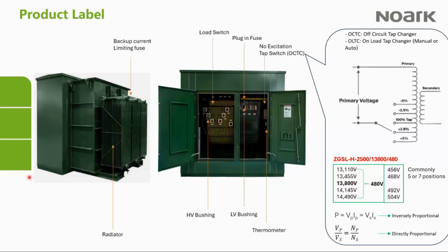So to start, just to show you the key parts in the pad mount transformer. On my left here, you have the radiator, which is what you use for cooling, with the fans, right? You have the backup limiting fuse just on the side of the transformer. And here, this is an open view. You can see the HV bushings and the LV bushings on the other side of it, the load break switch, the plug-in fuse, the tap switch, and all of these components are there for specific reasons. So I'm going to walk you through briefly what each of these means.